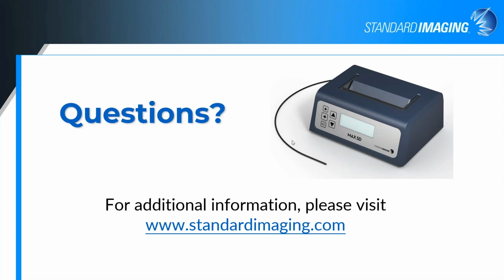So regarding the beam scan, yes, you would connect the Max SD to, so there's a triax cable that comes with the Max SD. You would connect it from the Max SD to the input of your beam scan electrometer. That's correct. The physical quantity that it detects, this is fluorescence that's generated in the scintillator based on the energy deposition. And so really we are measuring energy deposition via the fluorescence effect in the scintillation material.